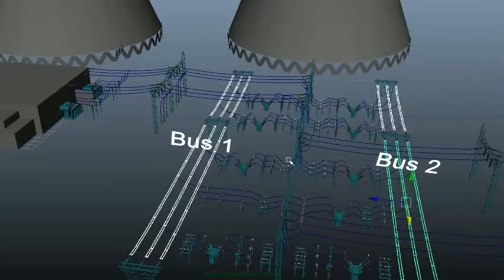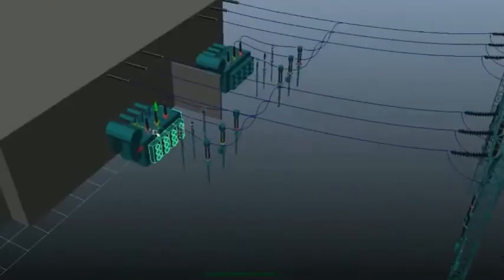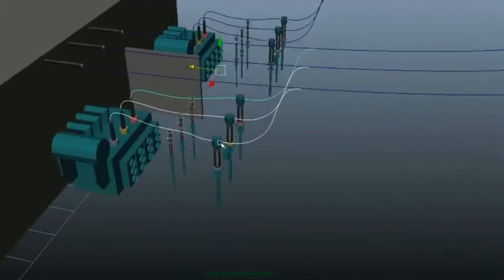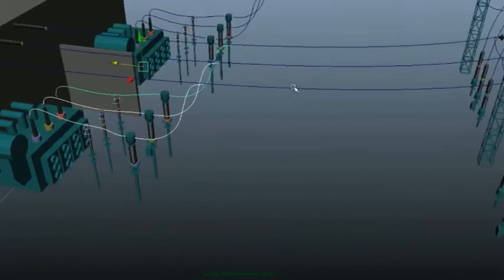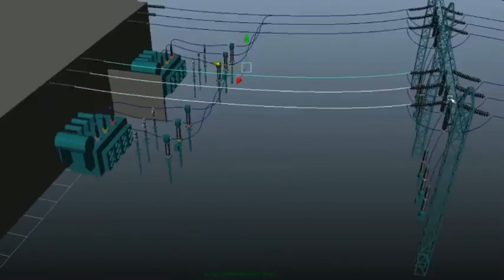Say this is bus 1 and this is bus 2. Let's understand the connections. After the voltage has been raised by the transformer of generated power, the high voltage line conductors are passed through the current transformer so that the current in the line can be measured. After that, these conductors reach the gantry.